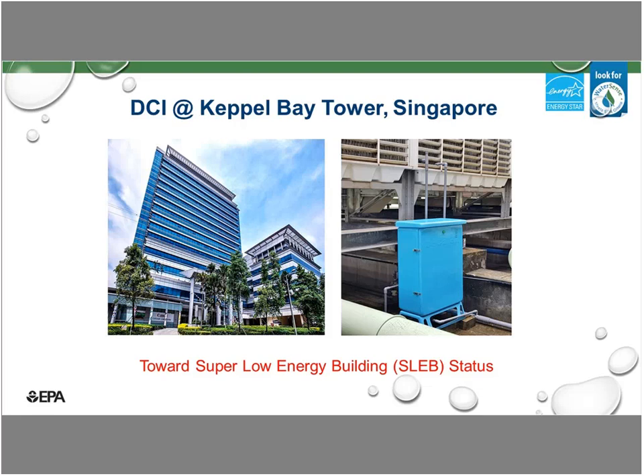You need to achieve at least, you must be able to run below 0.65 kilowatt per refrigeration ton, and then you must have a minimum of 8 cycles of concentration. That means your water consumption has to be very, very good to meet that kind of standard. So what the government wanted to do is to go further than the platinum standard. They're looking at trying to bring down the energy consumption by another 20% over the current best platinum standards.